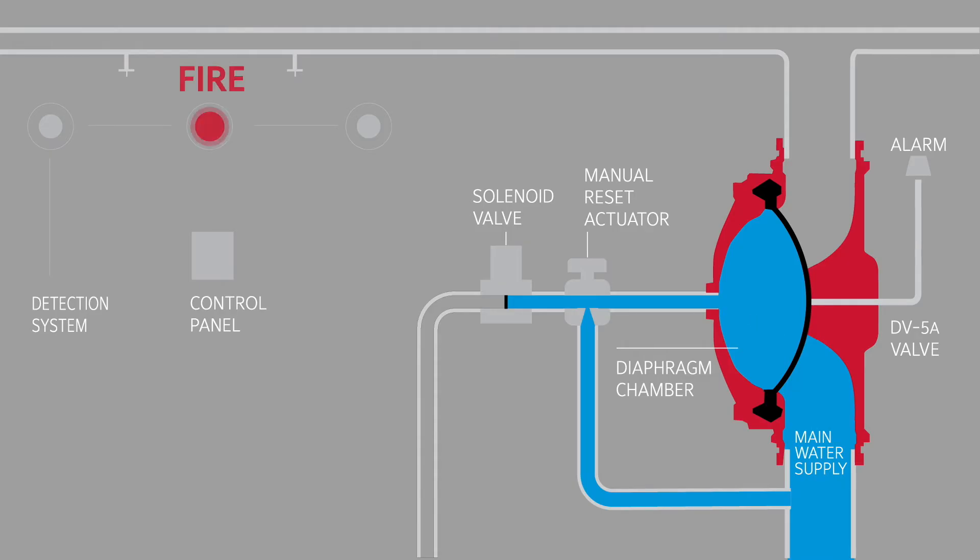When a fire sets off a heat or smoke detector, the detector sends a signal to the control panel. The control panel opens the solenoid valve, releasing water from the diaphragm chamber, allowing the higher pressure from the water supply to push the diaphragm open and flow through the system.